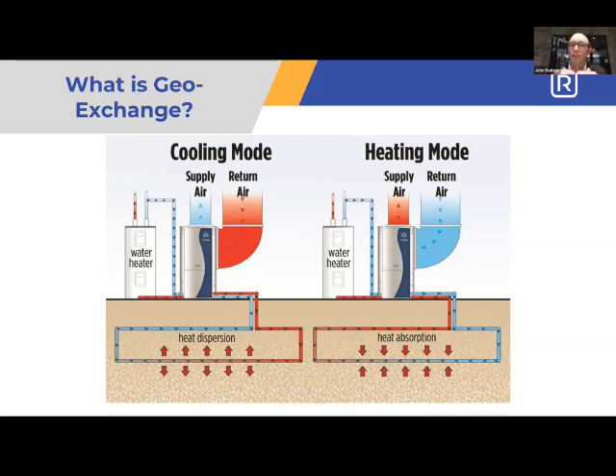What I mean by exchange, though, is that geoexchange is not a true source of energy in that you can deplete it. Every megawatt hour of heat that I pull out of the ground and push into your building, I have to put back at the end of the year. In the early days of geoexchange this wasn't well understood by operators, and there are some unfortunate examples of bore fields where they basically froze. They pulled so much heat out of the ground and weren't putting enough back in that the bore field essentially became a giant block of frozen rock and was useless as a heating resource.